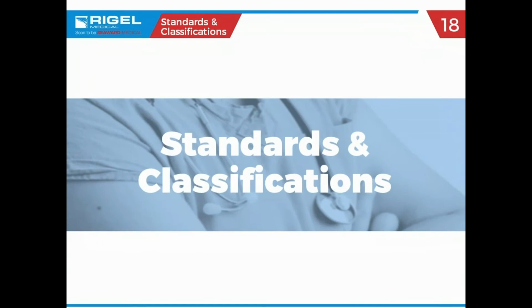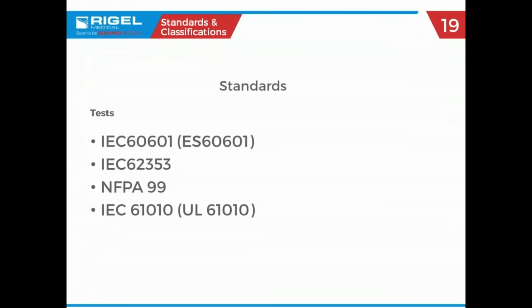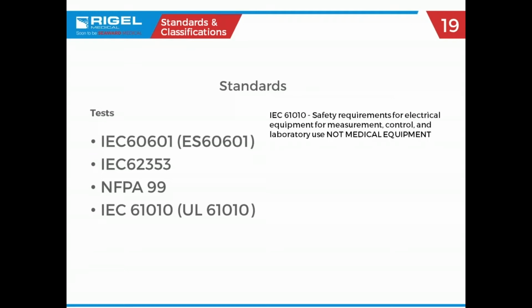So now, so much for the history. We're going to dive into the standards. So IEC 60601, ANSI equivalent ES 60601, 62353, NFPA 99, again, the prevalent test standards used here in the US. IEC 61010, anybody ever hear of that one before? Lab equipment. So not typically medical equipment, very close. They look at more potential voltage sitting on a case than touch current or leakage current. But those are the standards that you could run across in your daily endeavors.